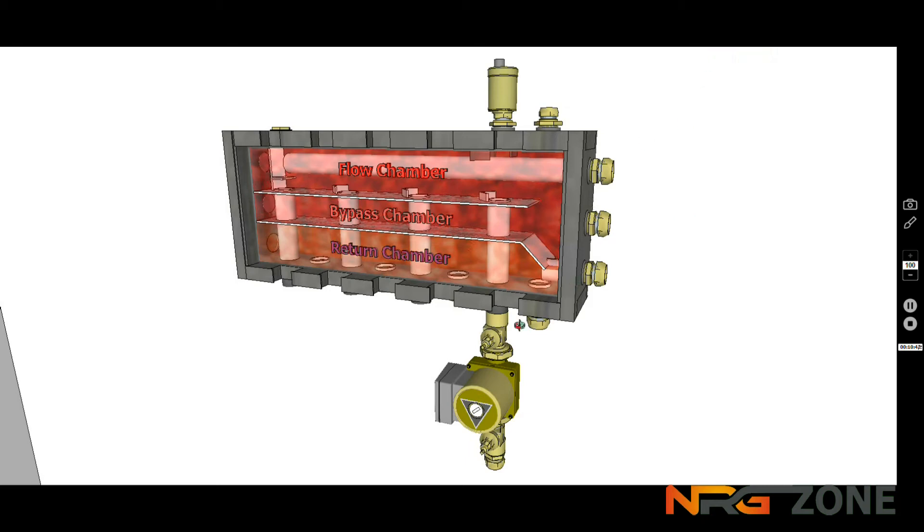You'll see that in this zone, it's just a straight pump with a straight connection back in, and there's no extra equipment. But if you were to use a zone for radiators or for underfloor, it's a good idea to put a non-return valve on the return that will stop any inadvertent circulation that might drift out onto the pipework, particularly if the pipework rises above the unit, as I'm going to show in this example.